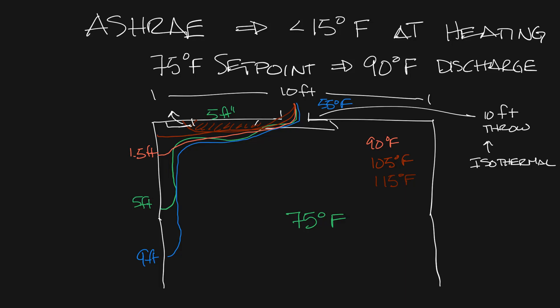So this is why hotter supply air temperatures in spaces with overhead diffusers is not a really good idea, so you should stick to the 15 degree recommendation by ASHRAE.